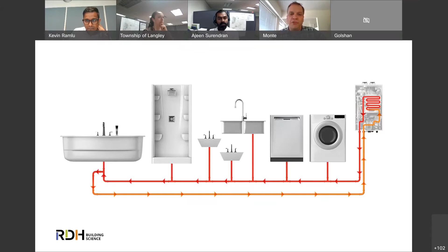The good news is this is one of many mechanical strategies where reducing the problem also costs less to build. If you minimize that system, lower pipe lengths, shrink pipe sizes, insulate the pipe better, maybe put a pump on that slows down in the middle of the night, you can have much less radiator effect in your building.